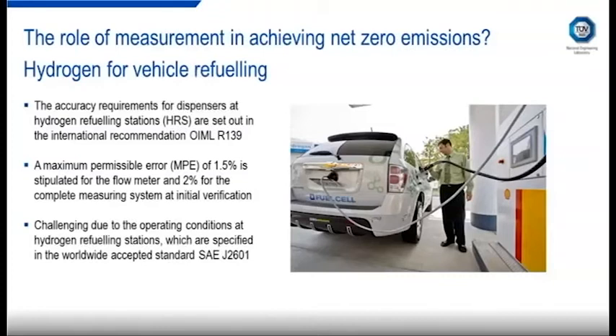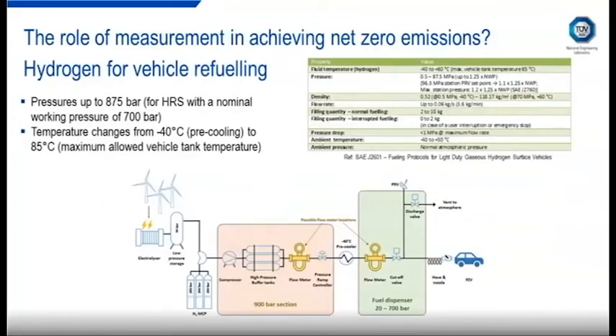The requirements for class 2 accuracy are that the overall measurements from the refueling station must be accurate to within a maximum permissible error of less than 2%, which corresponds to 1.5% for the flow meter itself. And this is actually really challenging because the measurement conditions at a hydrogen refueling station are not easy from a flow measurement perspective, as we can see.